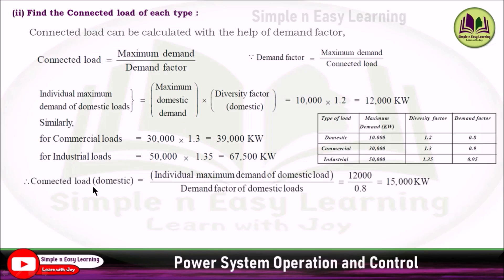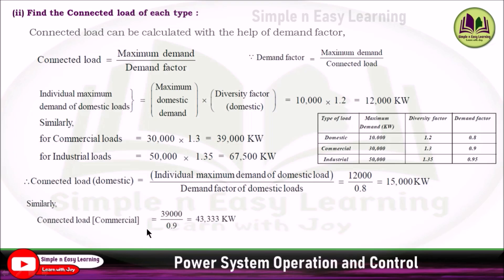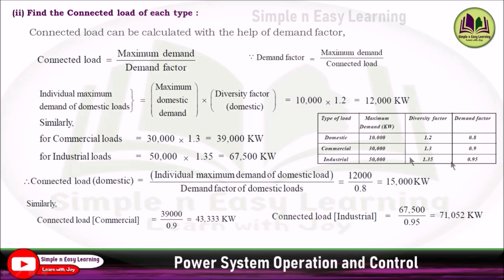The connected load for domestic equals the individual maximum demand of domestic (12,000) divided by the demand factor from the table, which is 0.8, giving 15,000 kilowatt. Similarly, connected load for commercial is 39,000 divided by demand factor 0.9. Connected load for industrial is 67,500 divided by 0.95, giving 71,052 kilowatt. This is how you calculate the connected load of each type.